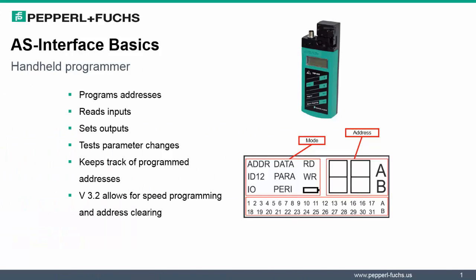Now, having learned about typical network arrangements, we need to understand what other tools may be needed in setting up AS Interface networks. The handheld programmer is a key component needed for setting up any AS Interface network. A handheld programmer can program any AS Interface module. It can be used as a diagnostic tool as well to read a module profile, set parameters, read inputs, and set outputs.